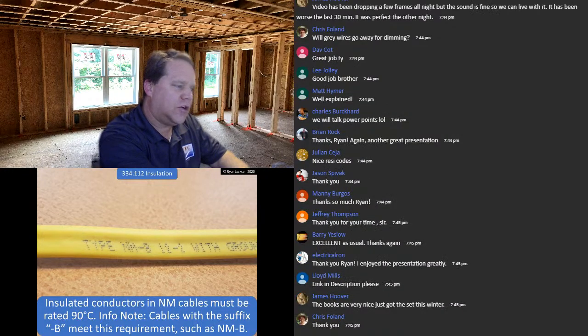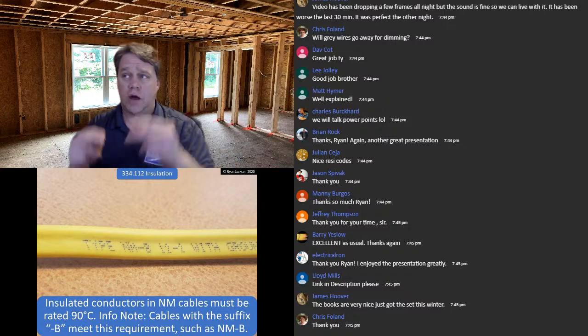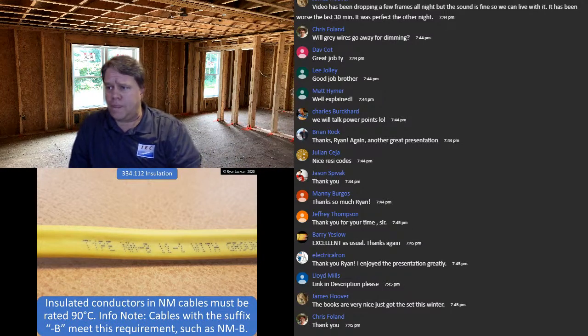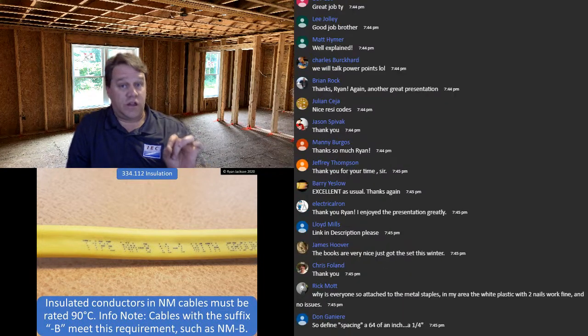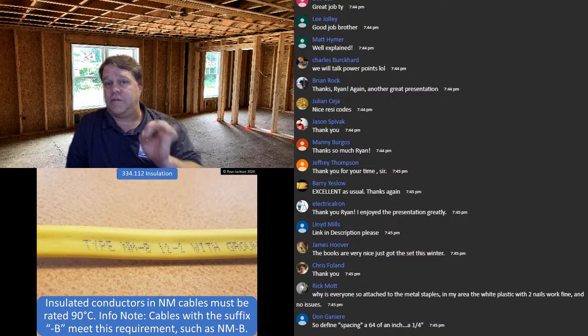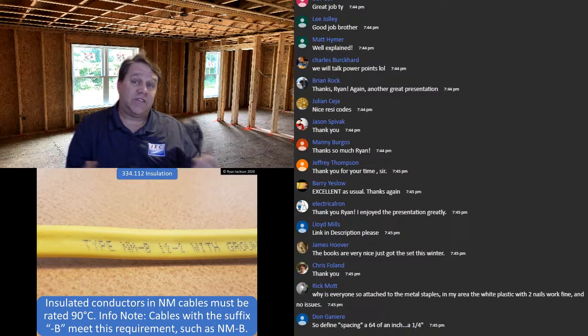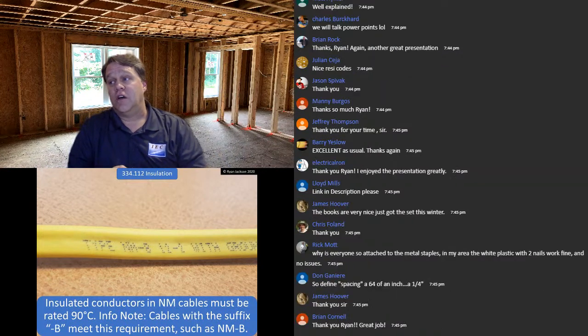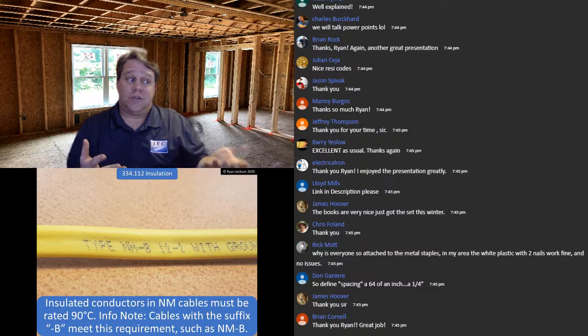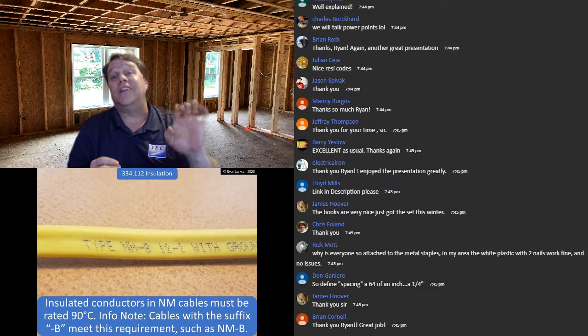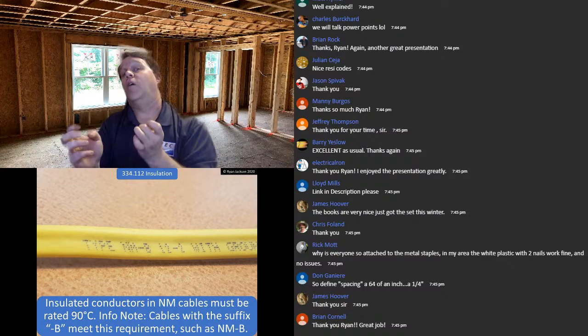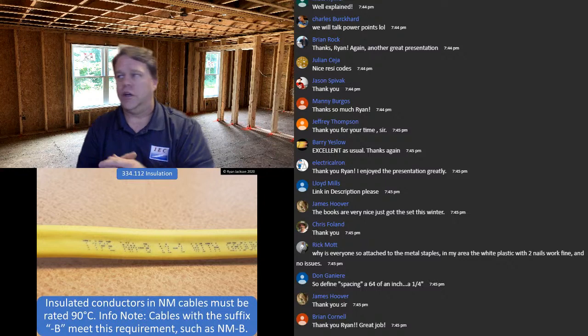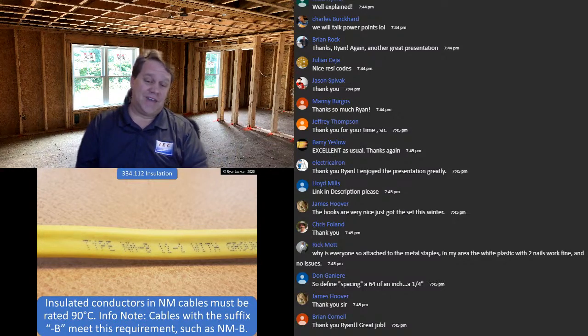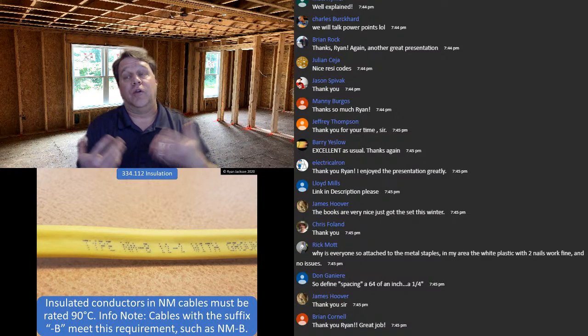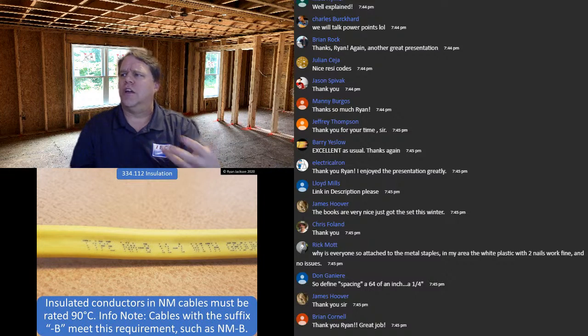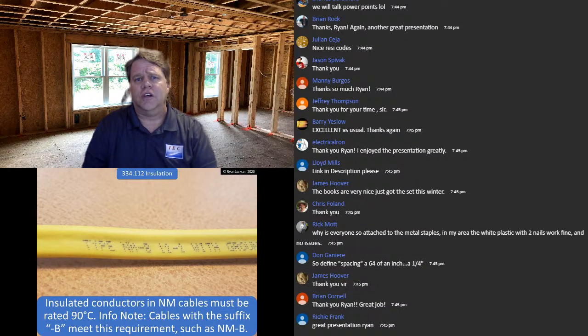Can these be used with old wire, no ground or reduced ground? So Chico, I'm guessing you're talking about the interconnector things. You have to be careful with that. If you go to 250.130C, as in Charlie, it has specific rules for extensions of branch circuit wiring. And basically, if you're extending old two-wire circuits, you have to extend it with a three-wire cable, and that ground wire has to go somewhere. You can't just put in a GFCI, right? So if you're replacing two-wire receptacles, go ahead and use a GFCI, usually. But if you're extending the wiring, that bare wire has to actually go to something. It has to go to an equipment grounding conductor terminal, grounding electrode system. Again, if you go to 250.130C, you'll see the list of items.